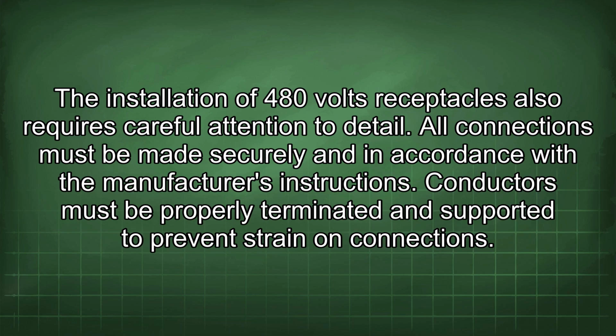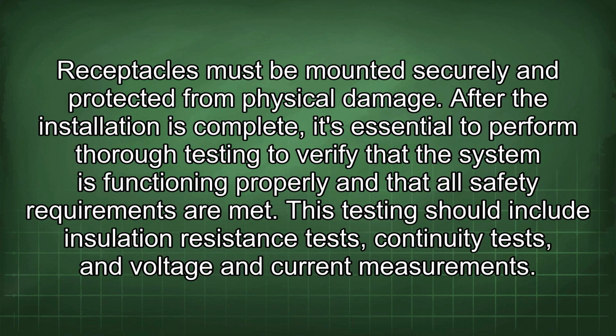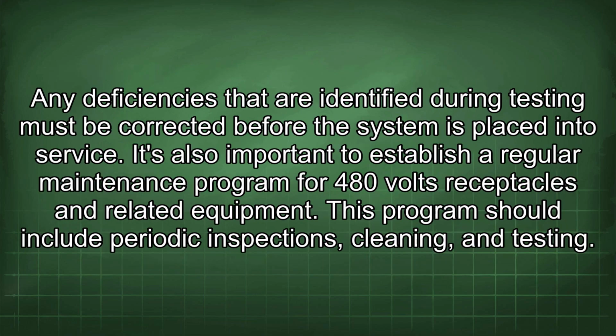The installation of 480 volts receptacles also requires careful attention to detail. All connections must be made securely and in accordance with the manufacturer's instructions. Conductors must be properly terminated and supported to prevent strain on connections. Receptacles must be mounted securely and protected from physical damage. After the installation is complete, it's essential to perform thorough testing to verify that the system is functioning properly and that all safety requirements are met. This testing should include insulation resistance tests, continuity tests, and voltage and current measurements. Any deficiencies that are identified during testing must be corrected before the system is placed into service.